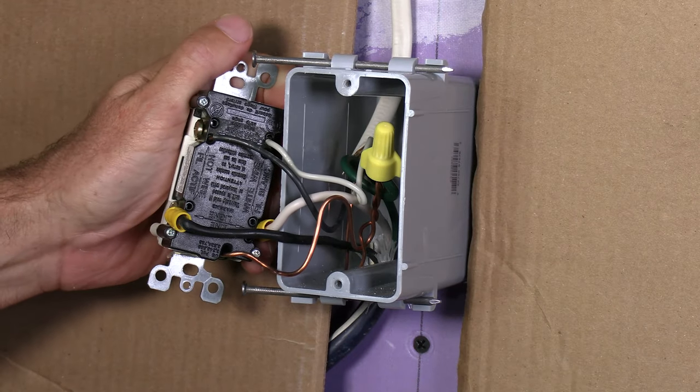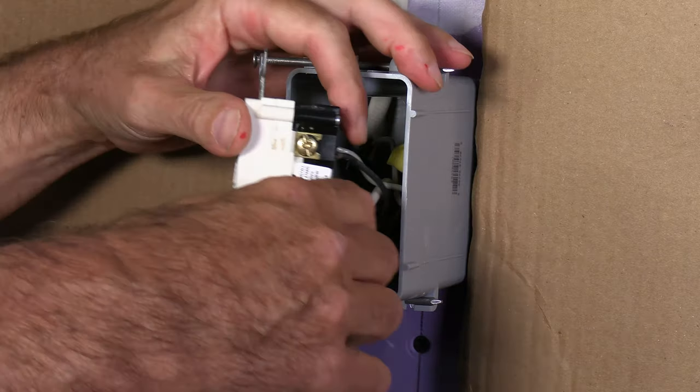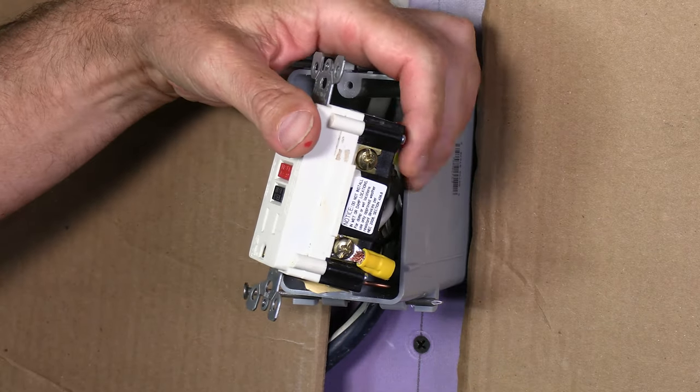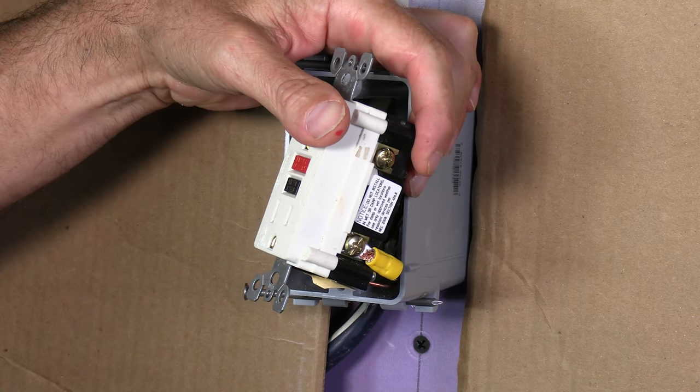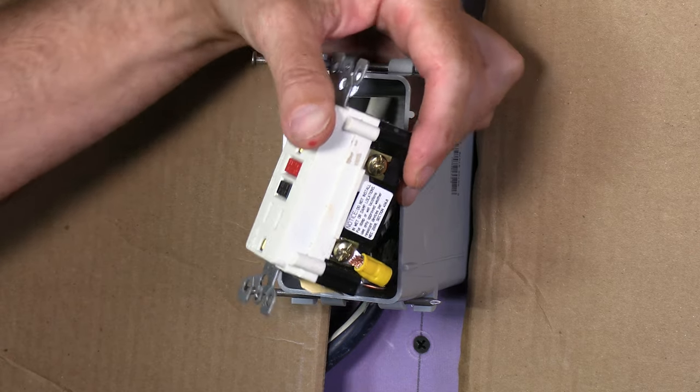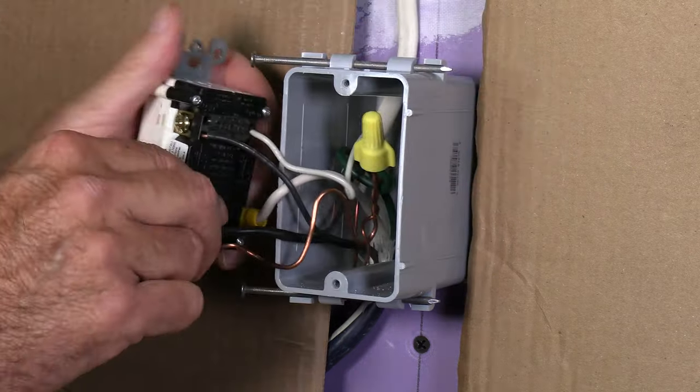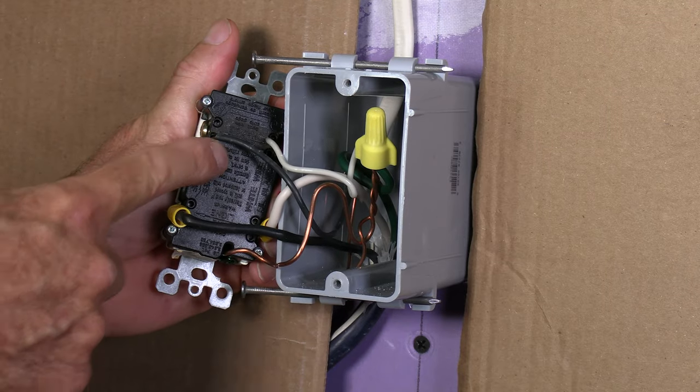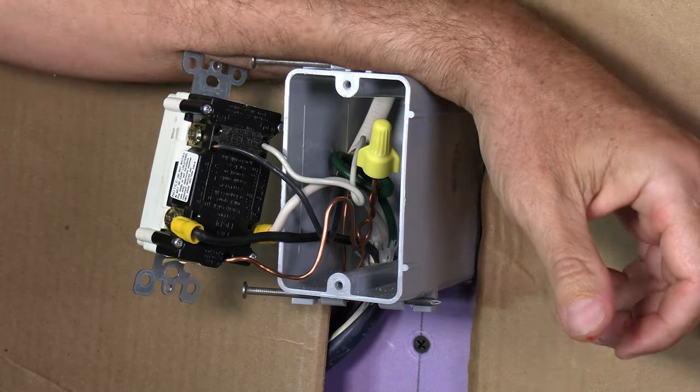There's not much else to it. One thing you do want to keep in mind is don't run GFIs in a daisy chain, hooking one GFI to another GFI to another GFI. You'll probably have problems with them tripping down the road every time it rains or gets wet. So keep that in mind. Put one GFI at the beginning of your run and the rest of the plugs that are hooked to the load will automatically be protected already. All right. So I hope this video has been helpful. If it has, please click that thumbs up and thank you for watching.